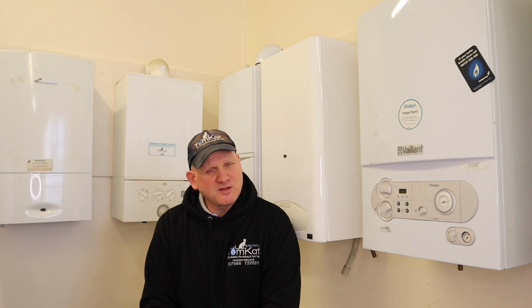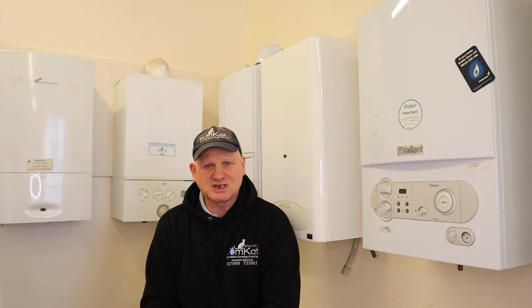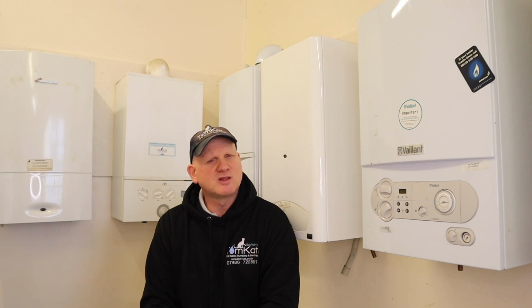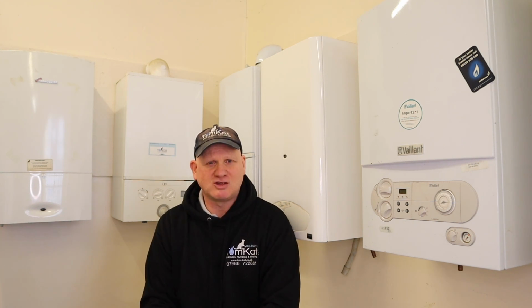So those are all the things that need to be taken into consideration when you're purchasing a boiler with a certain type of heat exchanger. So basically, in a nutshell, as we found out, a stainless steel heat exchanger is far more durable with larger waterways, but it is quite heavy and more expensive. And an aluminium heat exchanger has smaller waterways, is mainly cheaper to manufacture, and heats up the water a lot quicker than stainless steel.